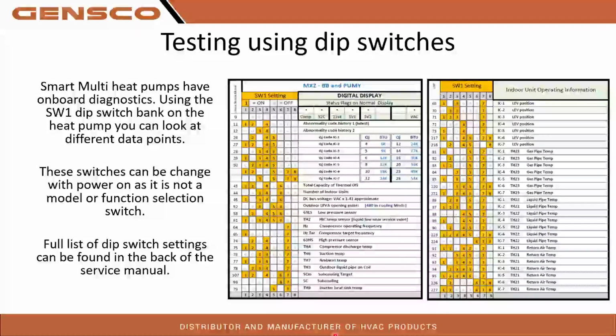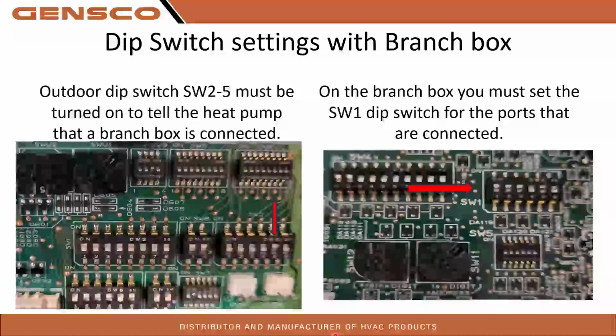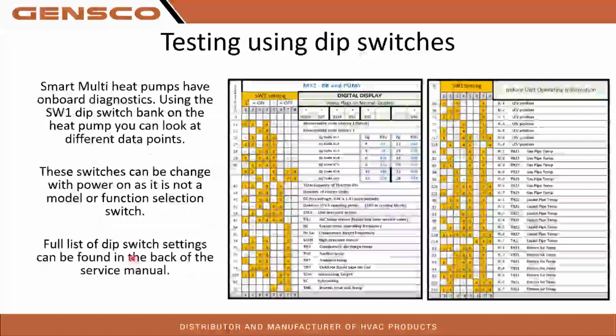On the Smart Multi, if you're seeing some of those common startup faults, that system does have its own onboard diagnostics. There's a dip switch bank on the heat pump. I think I had a picture of it back here. Yep, right here. SW1. It is an 8 switch bank, the largest of them, as you can see right here, middle row, left-hand side. This dip switch bank is used for onboard diagnostics. All of your other addressing, dip switches, and function settings need to be done with power off. This switch is pretty much one of two that can be changed with power on, because it is not changing any functions of the system. It is just looking at different data points.